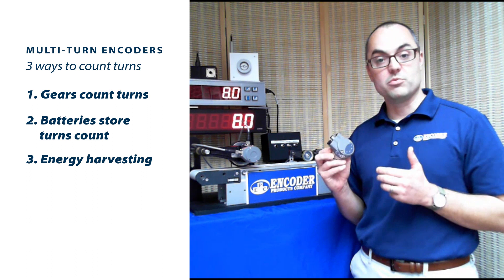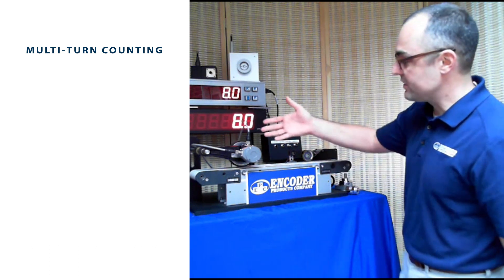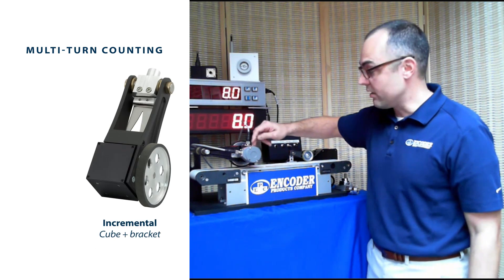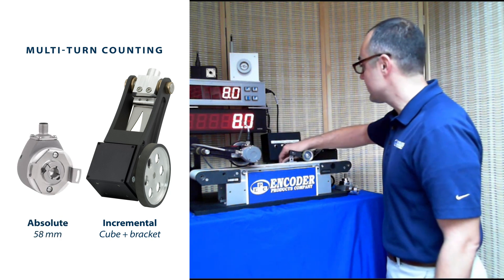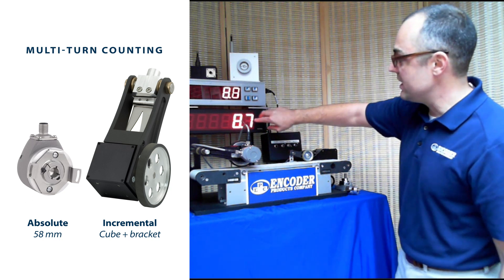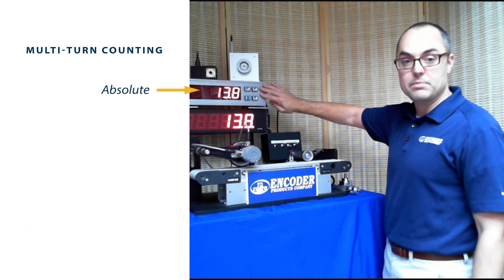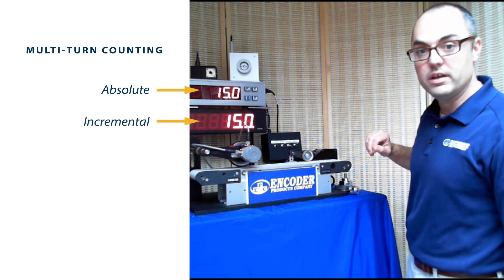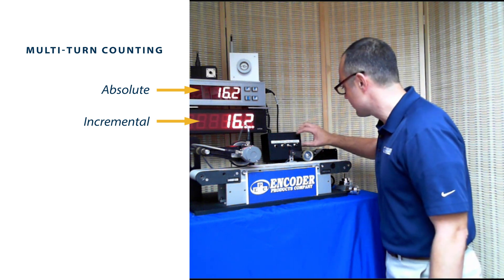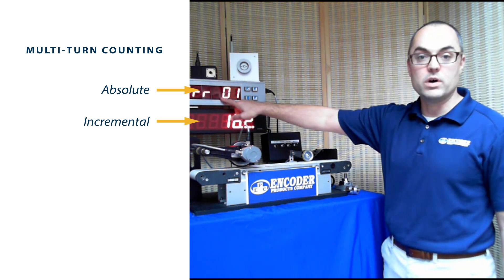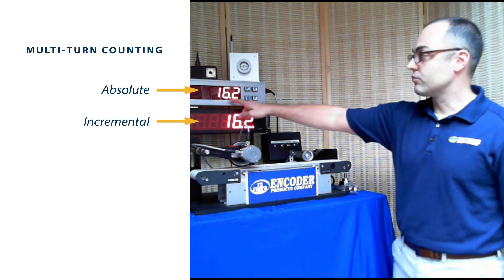Here we have a conveyor belt with an incremental cube encoder on it, and hanging off the back is our 58-millimeter multi-turn encoder. Starting the conveyor belt, you can see both displays are in sync — the top display is the absolute encoder and the bottom is the incremental encoder. If I stop the conveyor and turn the absolute encoder power off, you can see an arrow indicating it's no longer communicating. When I turn the power back on, it goes right back to where it was — it didn't forget, it didn't go to zero.